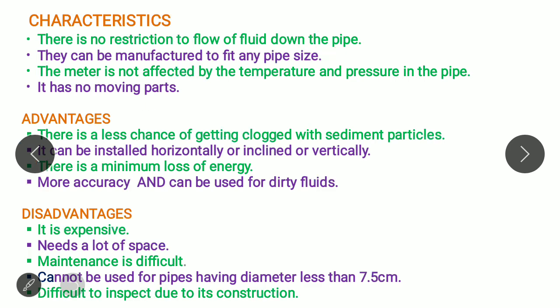A few characteristics that are inherent part of Venturimeter are, number one, there is no restriction to the flow of fluid down the pipe. They can be manufactured to fit any pipe size and the meter is not affected by the temperature and pressure in the pipe. It has no moving part. What it actually depends upon is square root of 2gh that is the pressure head difference, and the gravitational constant and frictional constant Cd, as we have discussed already in the formula and the derivation.